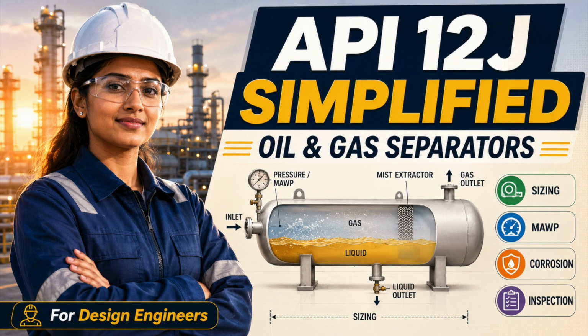The vessel drawing may show a clean, sharp interface between oil and water, but the real process may contain foam, solids, chemicals, and a broad emulsion layer. Your interface instrument is not measuring a perfect boundary. It may be trying to interpret a changing transition zone. This is why instrumentation cannot be treated as an afterthought.